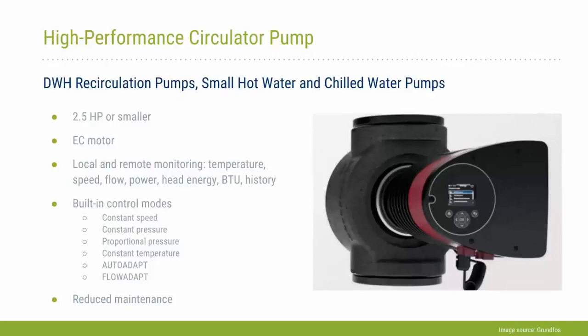One thing that I think is important to note is that the Energy Policy Act of 1992 set the first efficiency standards for motors, but they did not apply to motors that are less than 1 horsepower. And so for a lot of these pumps, including the ones you'll see in our demonstration here, they're going to have really low motor efficiencies and low power factors. And so moving to these modern state-of-the-art pumps tends to have greater energy savings than you'll see in larger commercial building applications. These are applied to motors that are 2.5 horsepower or smaller.